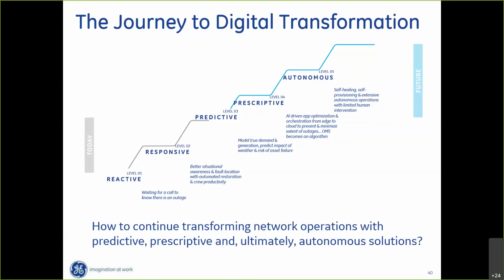And what we can do is put the logic, which could be at the control center or in the substation, that detects the fault, locates the fault, and then obviously the first step is to isolate the fault. You need to have a certain number of switches on your feeder to do this logic. That's why one of the blue boxes I had in the roadmap was a lot of the switches, right? So we open up switches on either side of the fault. That way we isolate it. Then we do upstream restoration and downstream restoration, okay?